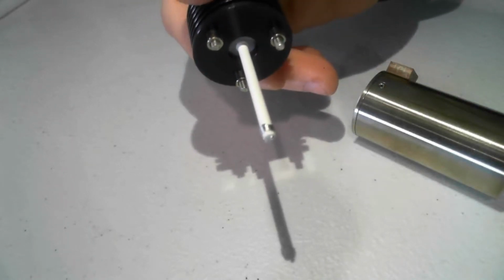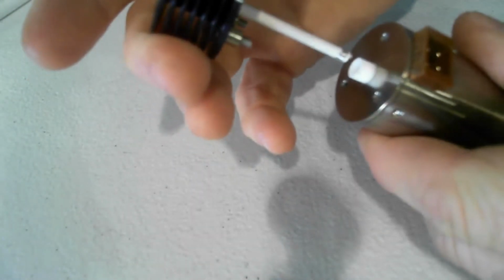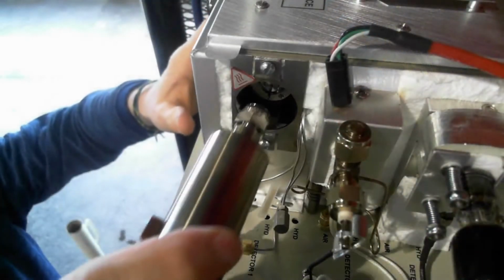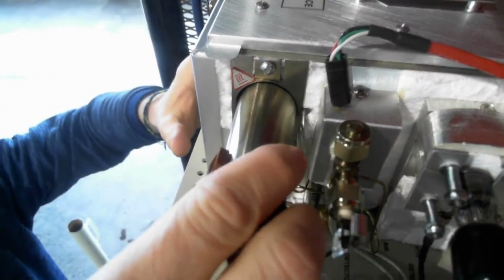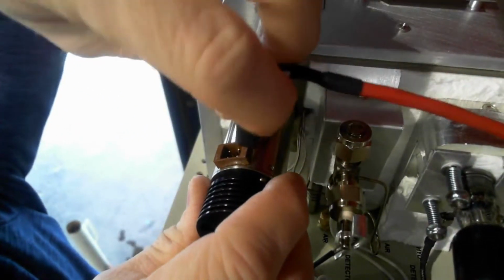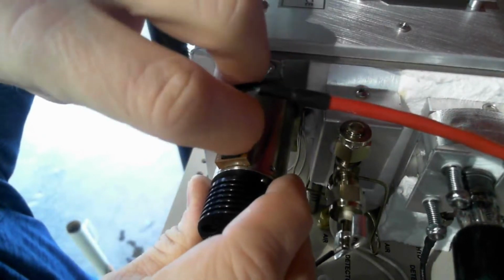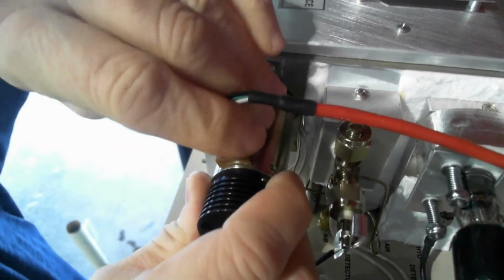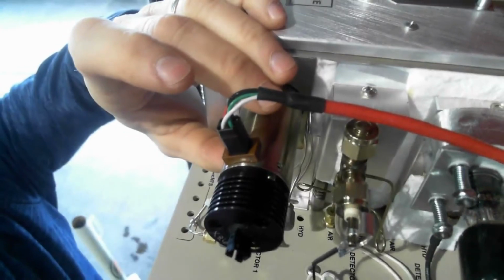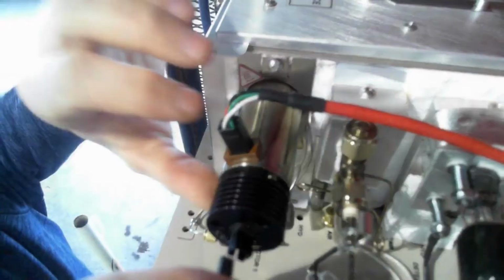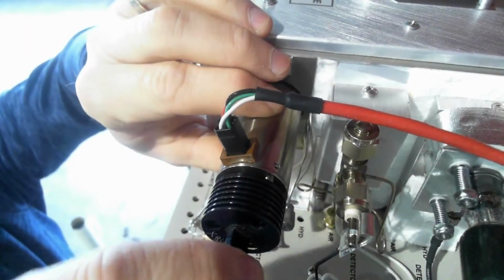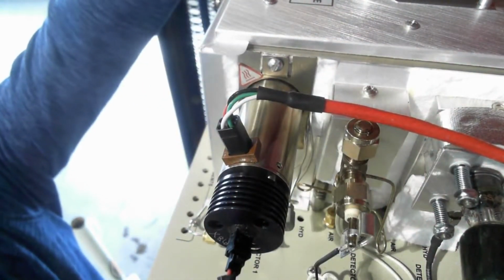When we have determined that the elements are clean, reassemble the detector cell by installing the probe assembly back into the reactor core and reinstalling the 3 screws. Then replace the detector onto its base of the GC, installing the heater cable coming in from the top and the signal cable on the end of the probe assembly. Then allow the XSD to heat up and stabilize for approximately 20 minutes before rerunning our 5 ppm TC performance test.